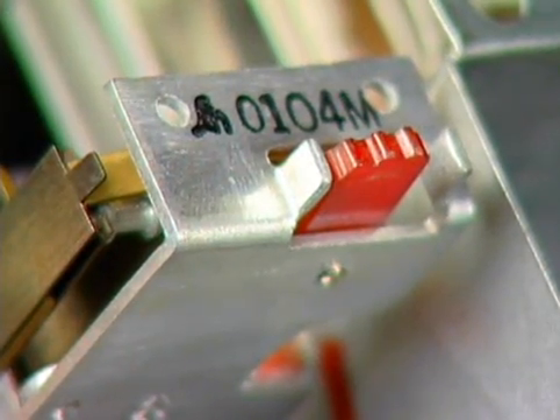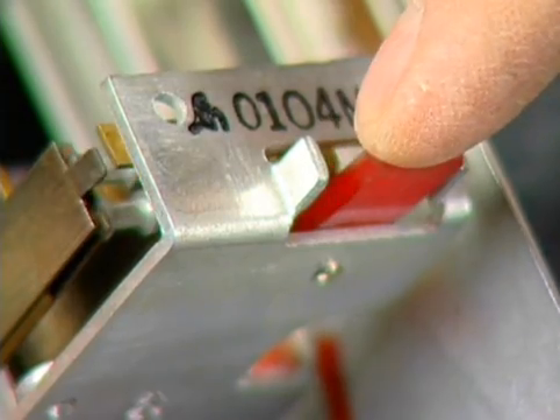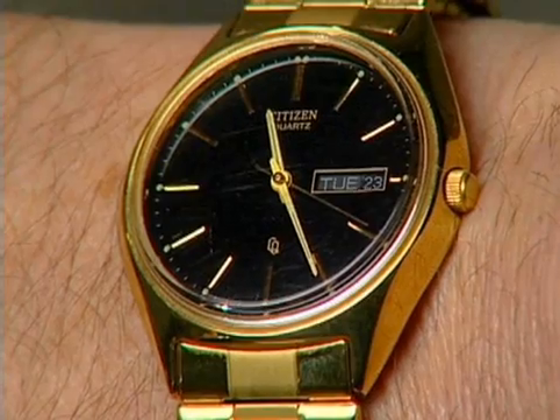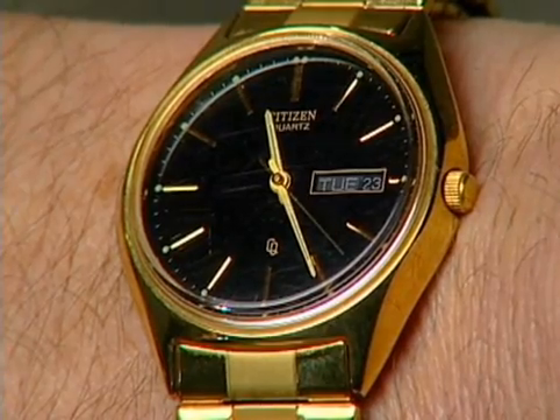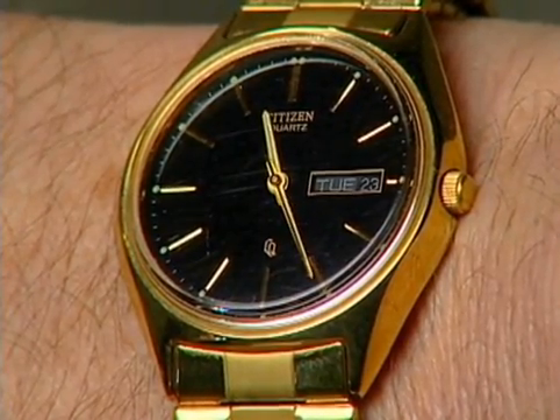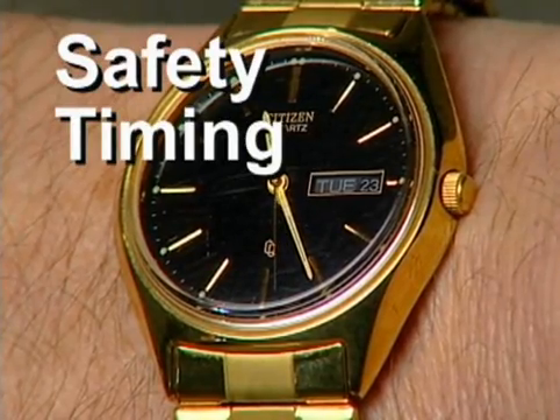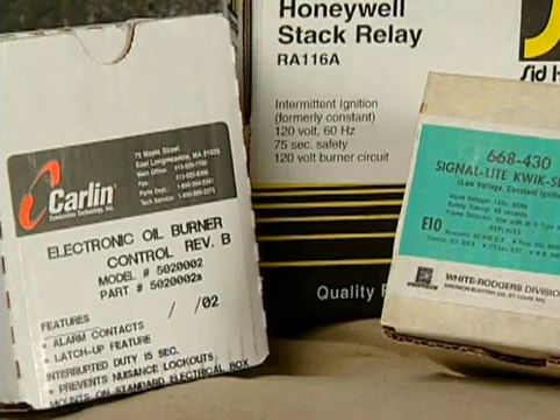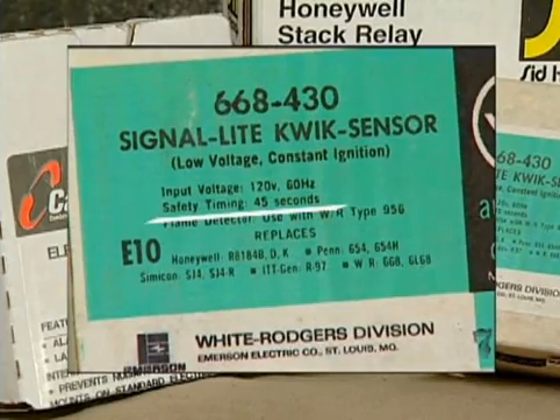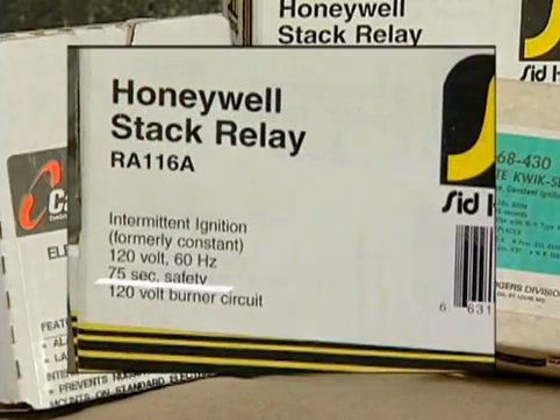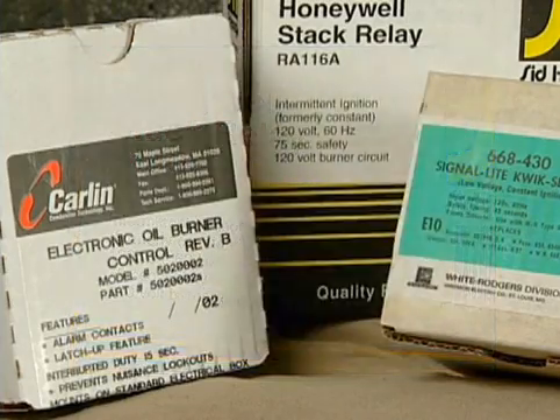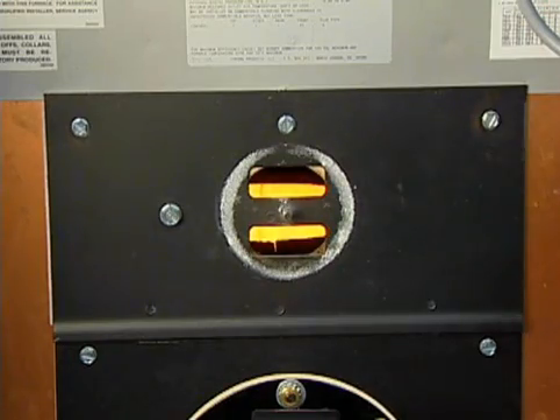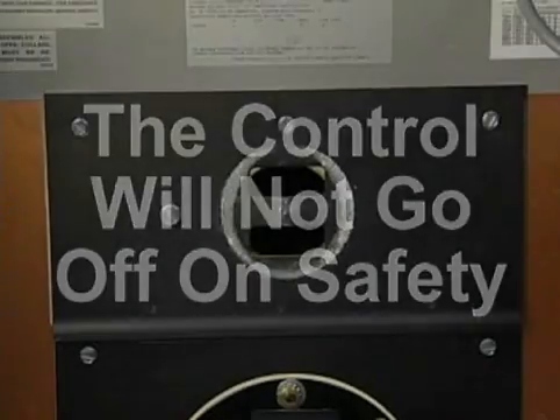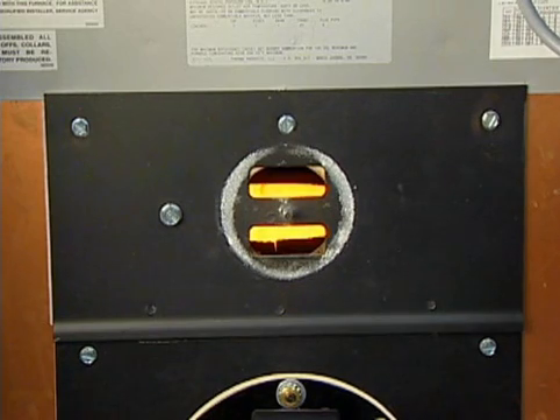Once the primary control goes off on safety, it must be manually reset before it can send power to the burner again. The amount of time that elapses from the start of a cycle in which flame is not established until the control goes off on safety is referred to as the safety timing. Slight variations from an individual control's stated safety timing often exist due to manufacturing tolerances, voltage variations, and temperature changes. It's important to understand that power outages do not affect flame detection. If power is lost during a running cycle, the control will not go off on safety, and it will normally re-energize the burner after power is restored.